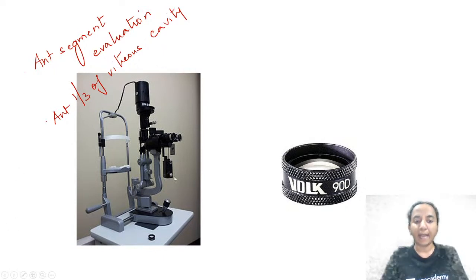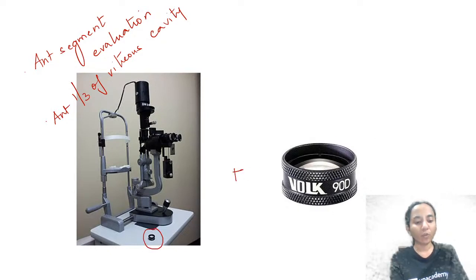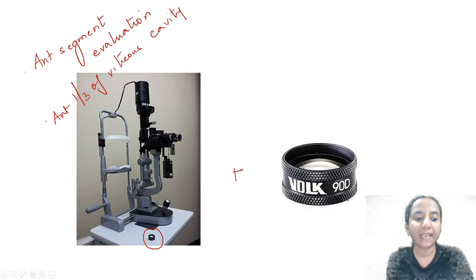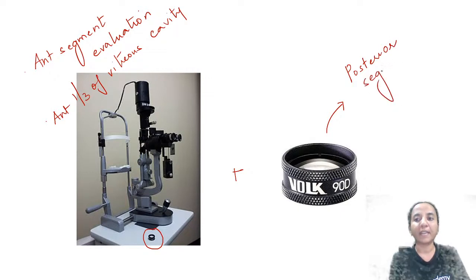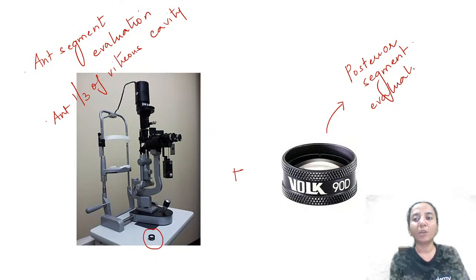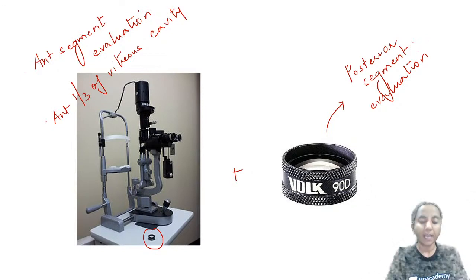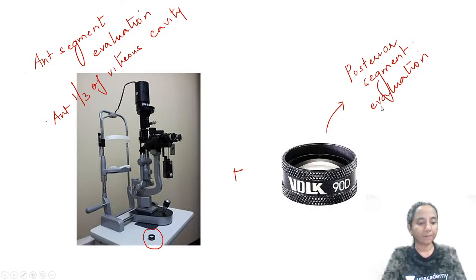With the slit lamp, if you use an additional 90D lens, you can also evaluate the posterior segment. So the slit lamp can be used for both anterior and posterior segment evaluation. Without the additional lens, you see the anterior segment and up to the anterior one-third of the vitreous; with the 90D lens, you can also see the fundus.